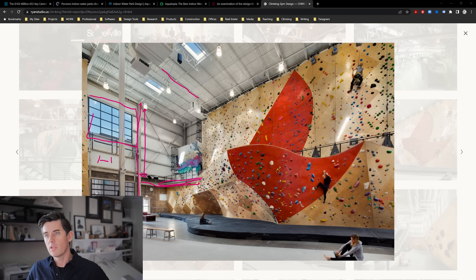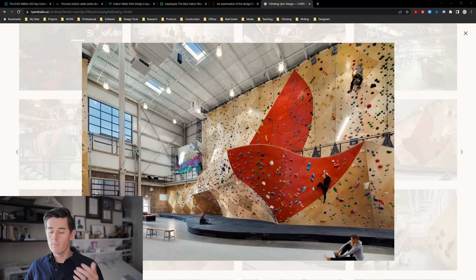The ceiling and roof is open web bar joist — not fire rated in the same way — because this is a lightweight part of the roof. On the other side of the project, wide flange beams span between columns because they're actually hanging the climbing wall from them in certain places — the most efficient engineering solution. Unlike the water park where the structure is all freestanding, here it's a mix of freestanding and attached to the building, which immediately creates different code requirements. We also added pre-filters, as seen in the water park, which are much cheaper to replace than the RTU they're feeding air into.